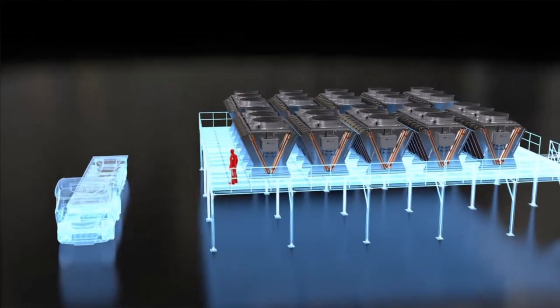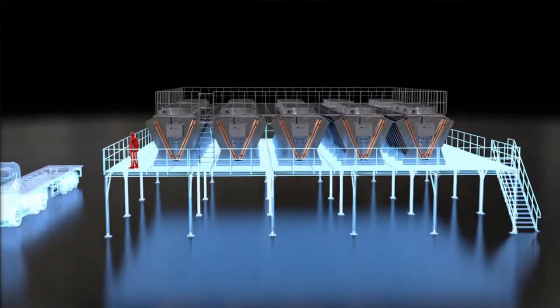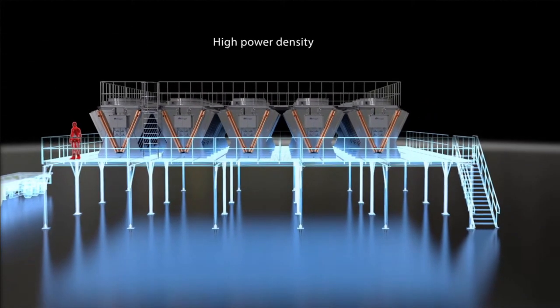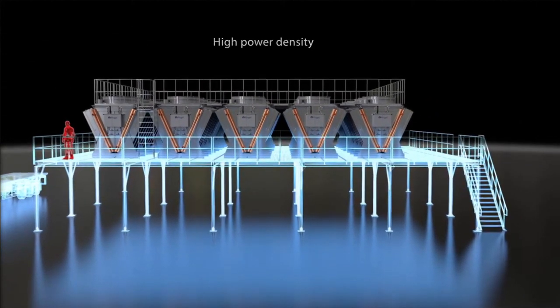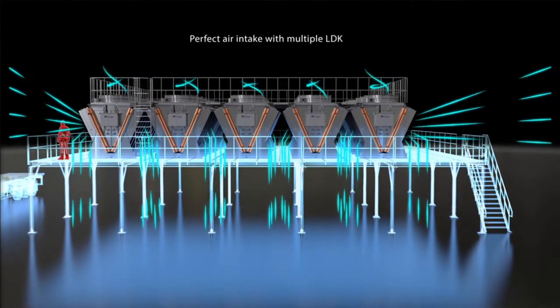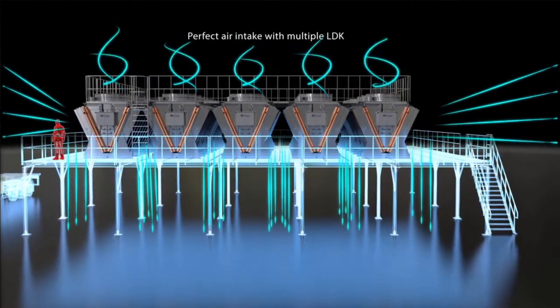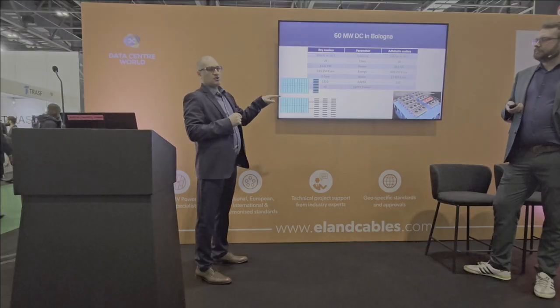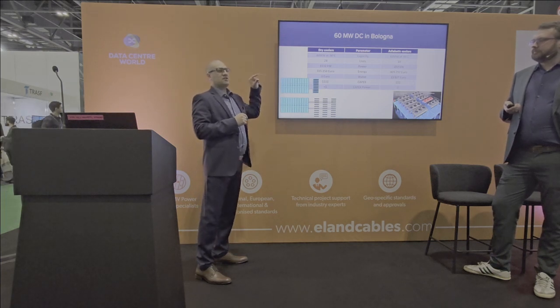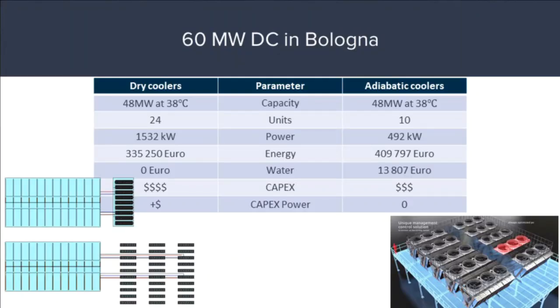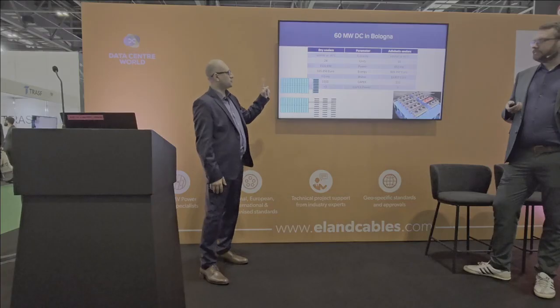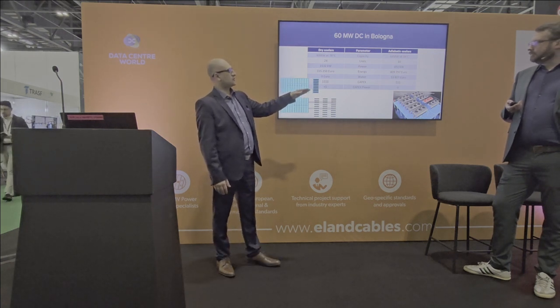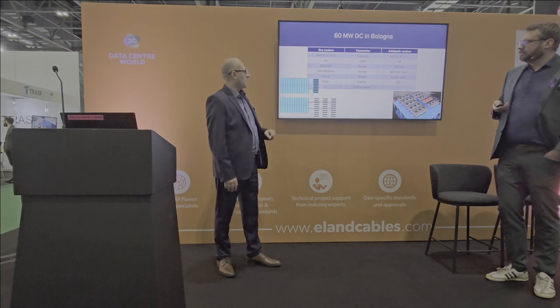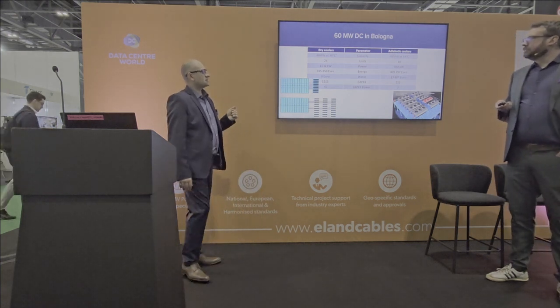At the same time, let's look for the capital investments for the dry coolers and for adiabatic coolers. In adiabatic coolers case, it is 30% lower. But there is also additional cost of covering this 1 megawatt additional power. And as we said before, 1 megawatt energy infrastructure cost is 1 million euro. So we should put additional 1 megawatt to the energy infrastructure. And in case of adiabatic coolers, there is no additional investment. And let's look next slide.